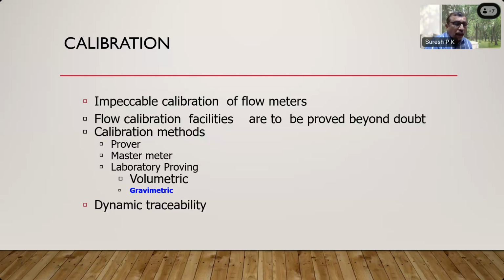Only difference is, the mass of the fluid which is passing through the meter is collected in a tank which is kept on a weighing machine, and the mass of the fluid is measured for a known time interval. Then the mass of the fluid which has passed through the meter during the same period is compared with the mass of the fluid. I will show you the gravimetric method and volumetric method as available in FCRI. I have a short film on that. I'll show you that. And we have a dynamic term called dynamic traceability.